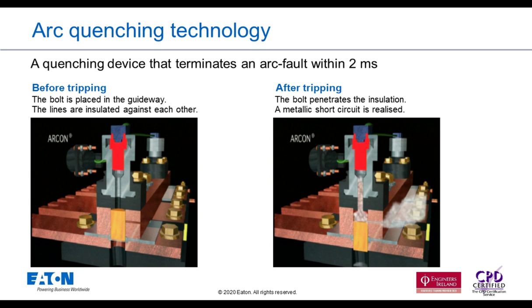In terms of detection of the arc by the optical sensors and the current monitoring, typically that takes around 2 milliseconds, and then to create a bolted dead short across the lines takes typically another 2 milliseconds. So within 4 milliseconds, the arc is diverted to a dead short and mitigated in the system. This reduces the time that an air circuit breaker would typically take to actuate, and in the background the sensing equipment is also sending a signal to the air circuit breaker to open. So you've got a much more controlled system going forward.